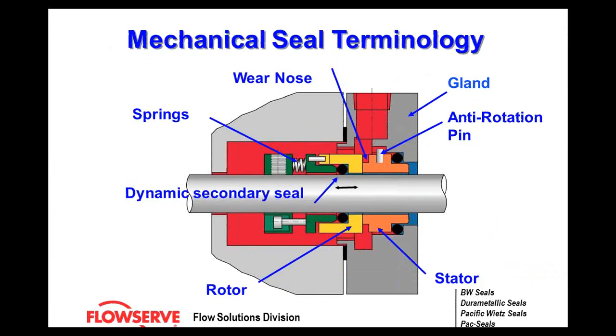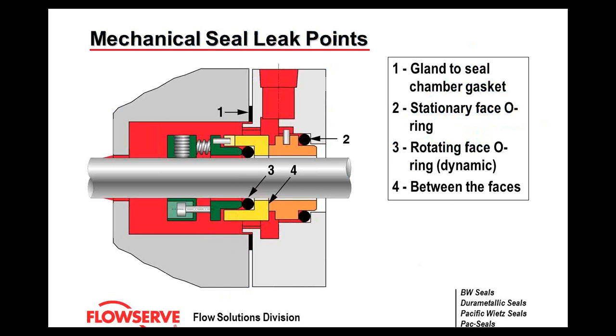Some typical mechanical seal terminology: the springs, rotor, and stator; the anti-rotation pin which holds everything together; and the gland — adaptive hardware that allows you to bolt your seal to your pump. The wear nose is always on the softer of the two face combinations — if you have silicon carbide versus carbon, the wear nose will be on the carbon. There's also a dynamic secondary seal, or dynamic o-ring, on pusher-style seals. Anywhere there's a gasket or o-ring, there could be a leak point.